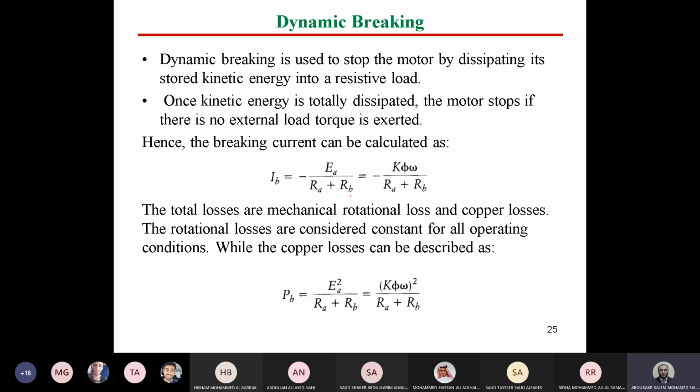So the higher the braking resistor, the lower the braking current. Right or wrong? Is it clear? If we add a higher braking resistance, this will reduce the braking current. But what about the energy and the energy consumption, or we can say the time of braking? Is it going to be lower or higher with a small current?